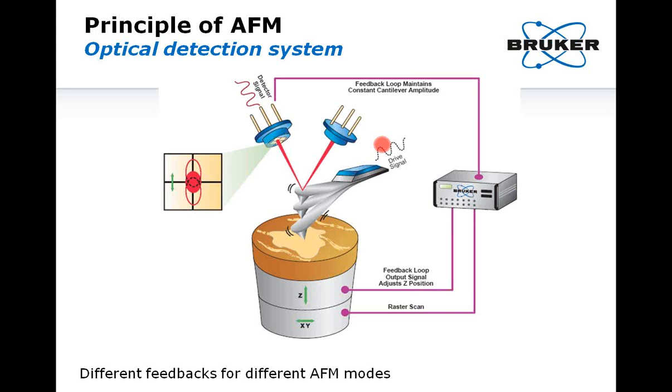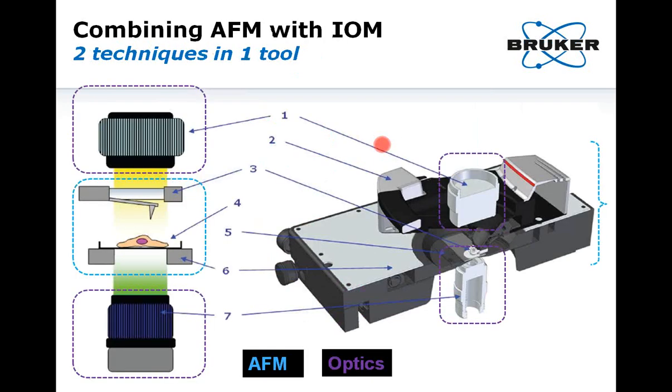This cartoon represents the optical deflection system, which is the most commonly used worldwide. AFM can be combined with inverted optical microscopy techniques: the optical stage can simply be replaced by the AFM stage, which moves the sample in XY directions while the tip remains idle. The large optical access allows coupling to a wide range of condensers and objectives. In the setup: number one is the condenser; two is the AFM head with large optical access; and three is the cantilever holder with mounted tip.